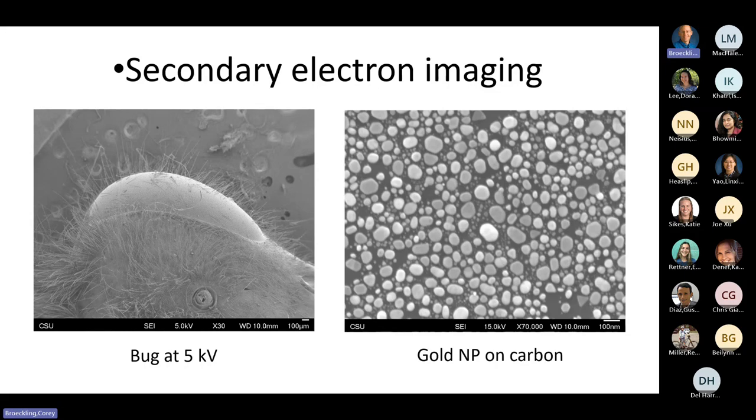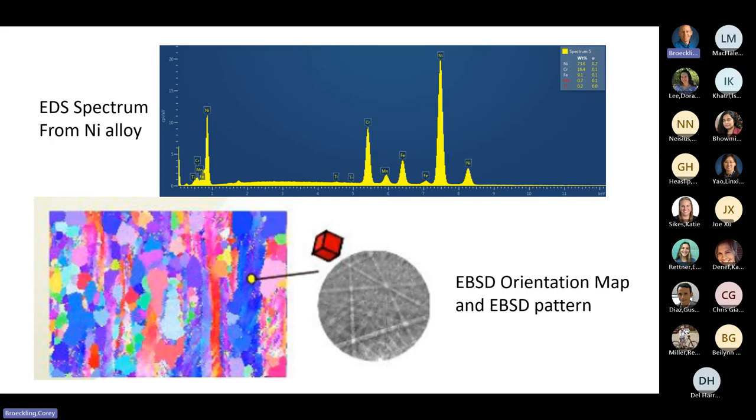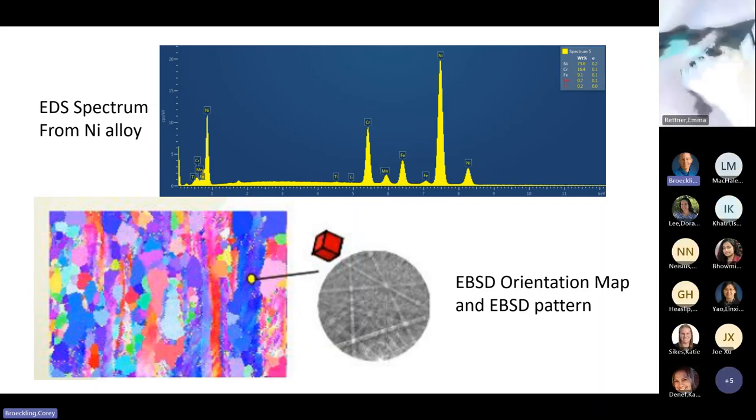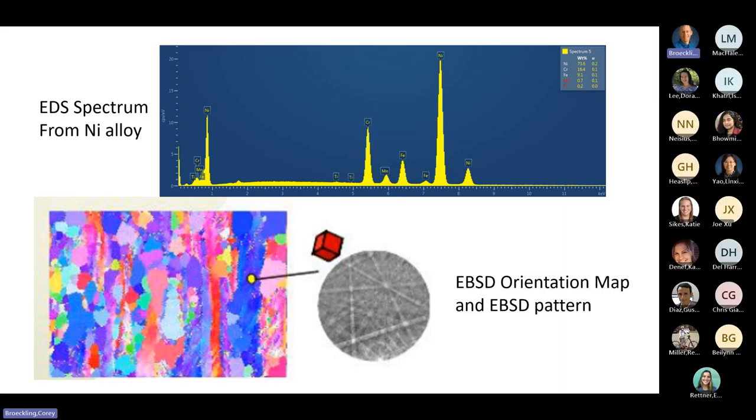We can do EDS spectra. It basically does the elements from beryllium up to uranium. The big problem is people take those numbers of quantification, they believe that because the computer spits it out, it's good. And it's not. But if you think you have strong, medium, weak, and very weak, and you're happy with that level of concentration, then you're pretty satisfied.